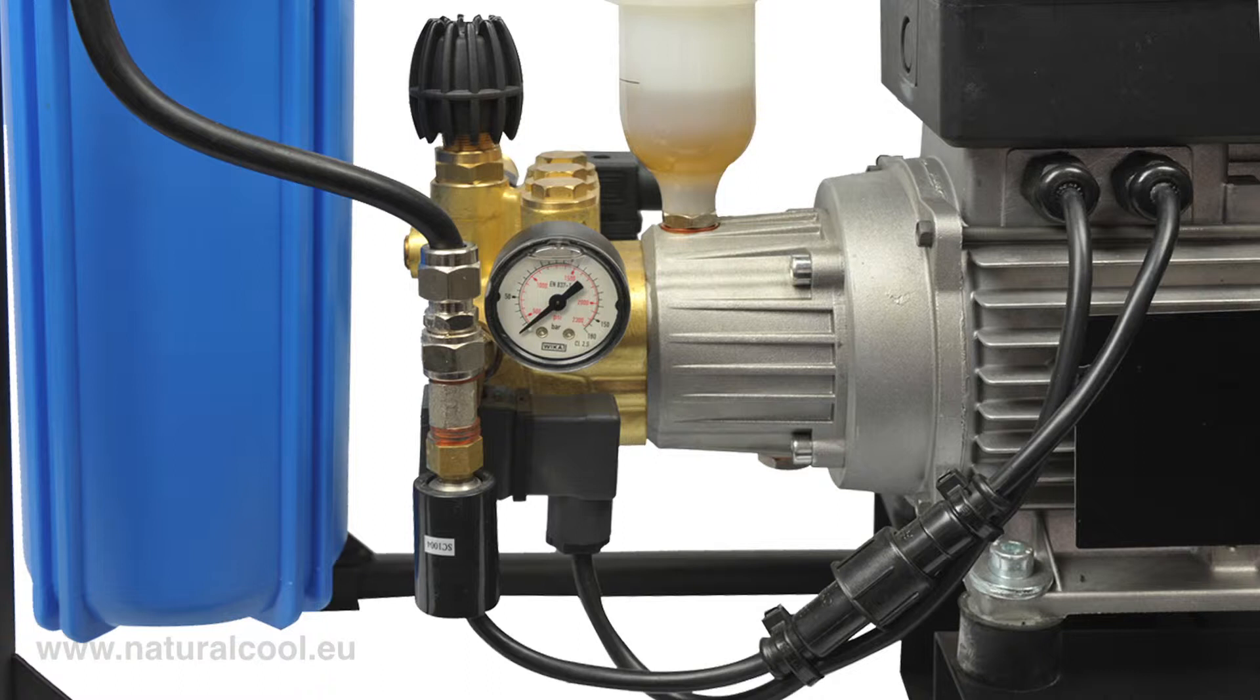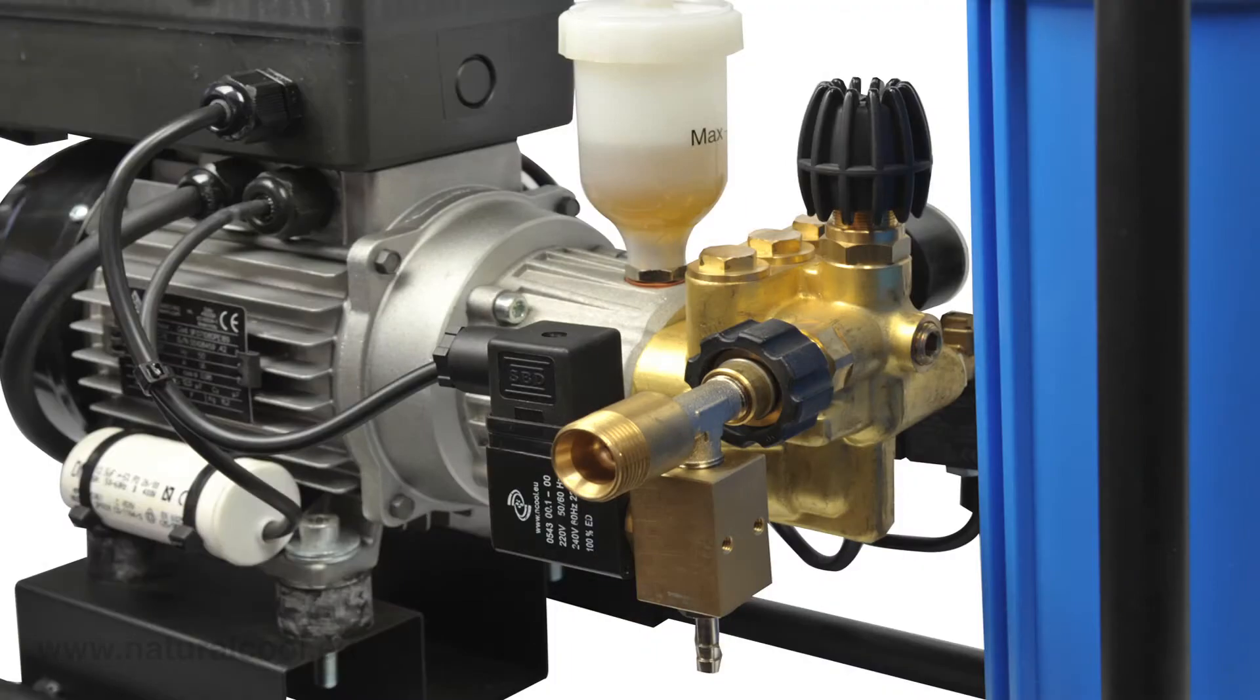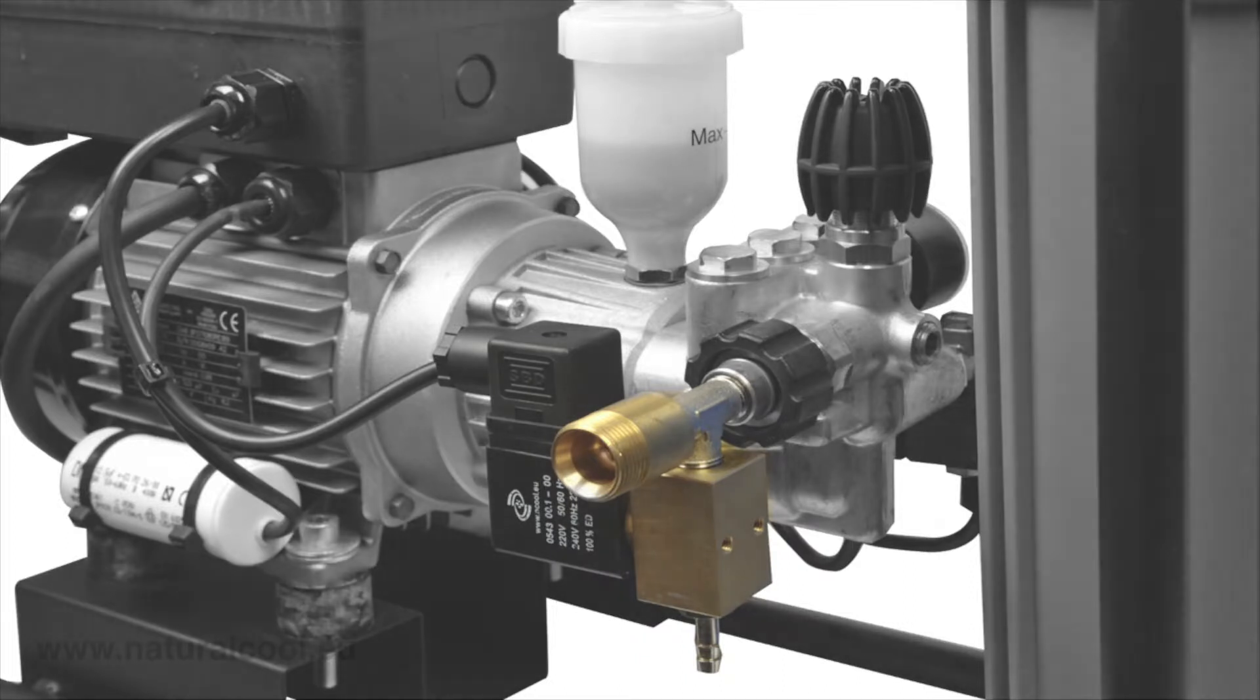A manostat is mounted as standard that stops the pump in the case of a lack of water, together with an inline safety solenoid that stops the water flow whenever the pump is switched off. A further solenoid is present in the high-pressure part that has the task of depressurizing the line every time the control unit is not operating.